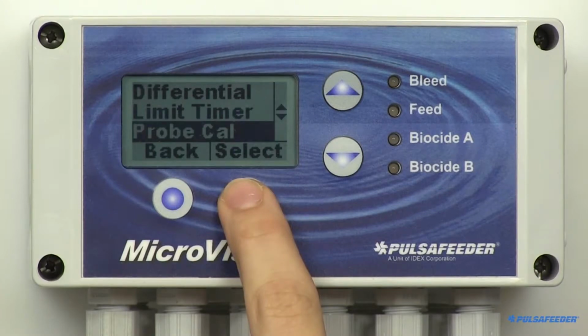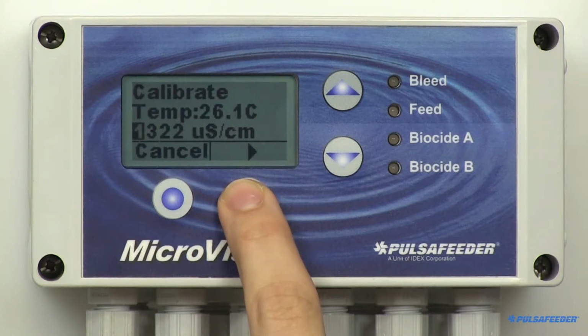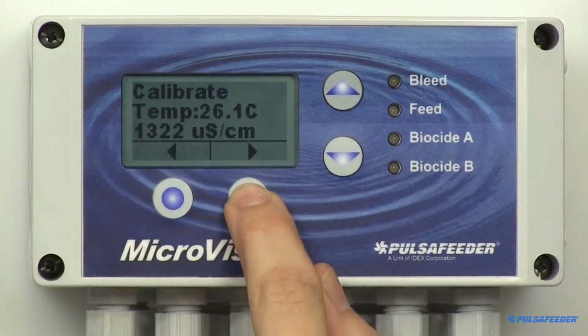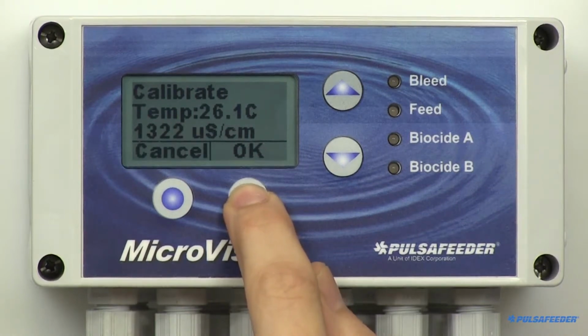Probe calibration. Some important information to remember. The conductivity probe is very sensitive to temperature changes. Always allow the probe to adjust to the temperature of your test solution or sample for approximately 10 minutes. Only use a temperature compensated calibration meter for calibration. It's always a good idea to calibrate your probe as close to the set point value as possible for accurate control. From the conductivity menu, arrow down to the probe cal and select it. You will see the probe's temperature displayed and the conductivity value in microsiemens. Use the arrow buttons to enter the current conductivity value, then hit Enter and OK.